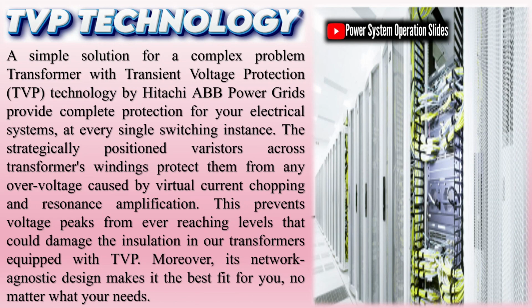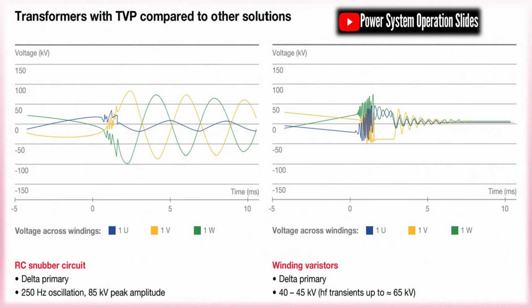The stress from extreme transient voltages can damage a range of magnetic equipment in the network, including transformers, motors, pumps, and measurement equipment with repeated switching over time. Switching transients are perhaps the worst voltage stress that a transformer could be subjected to. Due to complex system variables, the exact nature of the damage was often difficult to predict or even identify. There have been some proposed solutions like RC snubber circuits and surge arresters.